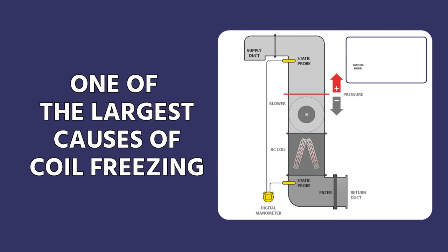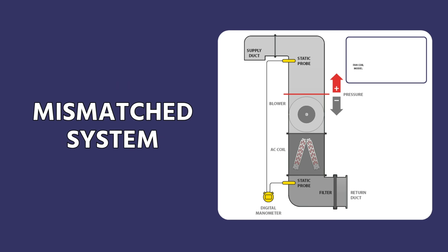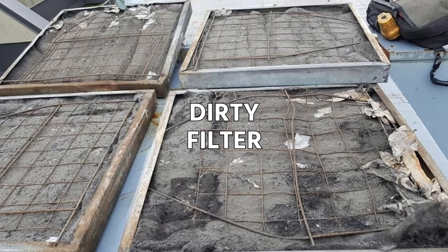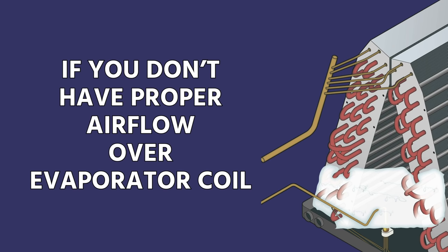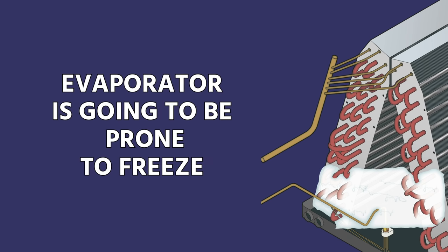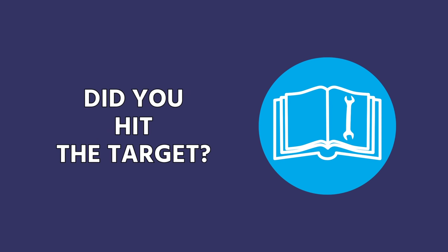Airflow is one of the largest causes of coil freezing, especially consistent coil freezing. Getting the airflow settings wrong, having a mismatched system, having ductwork that's too small, a dirty blower wheel, a dirty filter — those are the things you want to pay attention to first. If you don't have the proper airflow over your evaporator coil, that evaporator coil is going to run colder and is going to be prone to freeze. Always read the manual for the equipment you're working on, and you need to know what the proper airflow should be in order to know whether or not you hit that target.